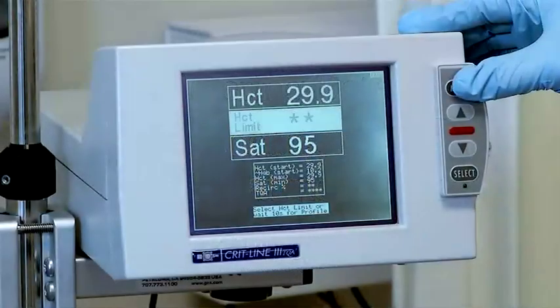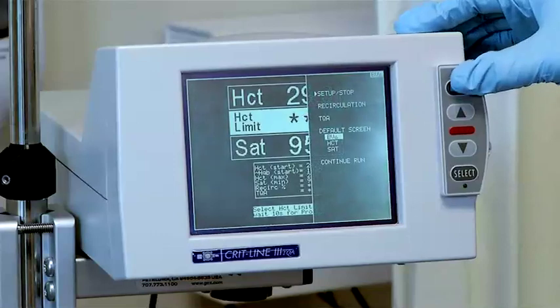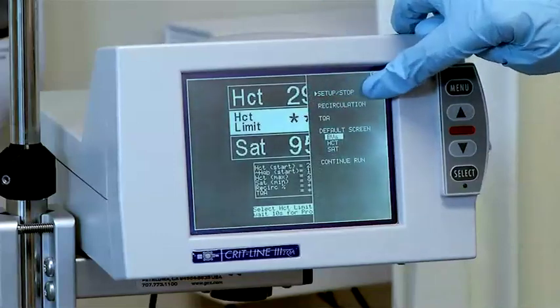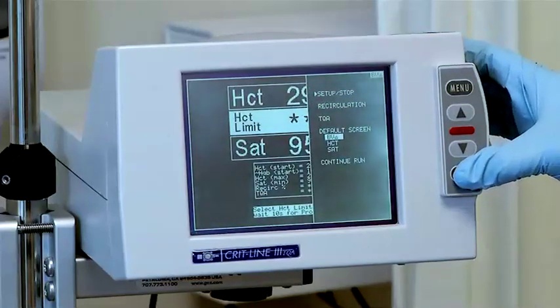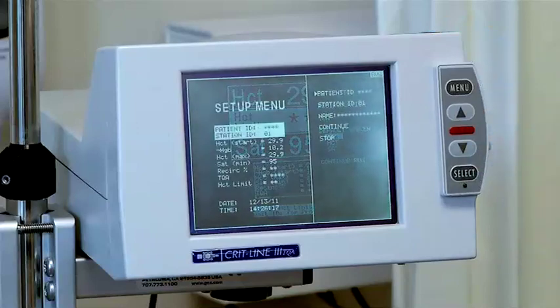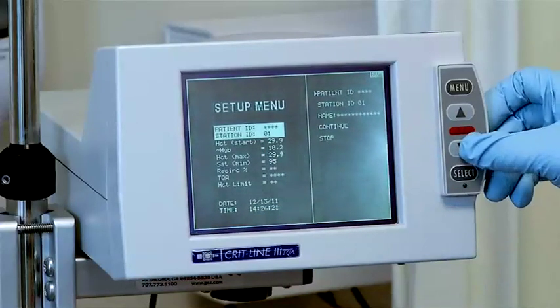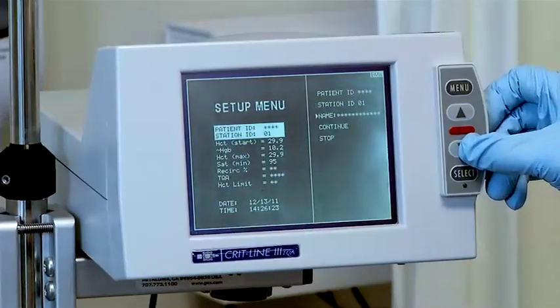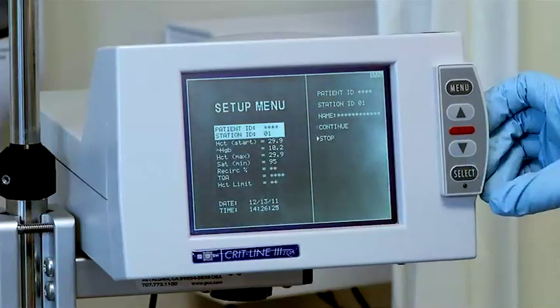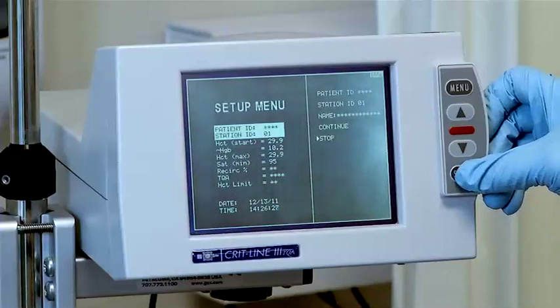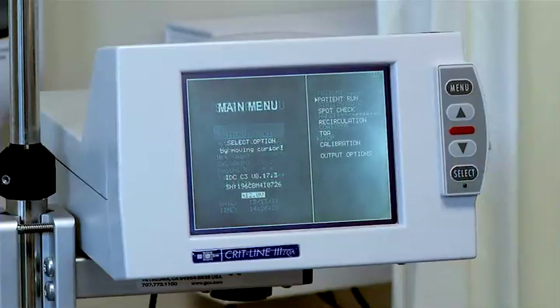In addition to being able to change the default profile screen, the split startup screen allows you to exit treatment by moving the cursor to Setup Stop and pressing the Select button, and you will be directed to the Setup menu. Review the information in the Setup menu and make any changes if desired. Then move the cursor to Stop and push the Select button to end the treatment.